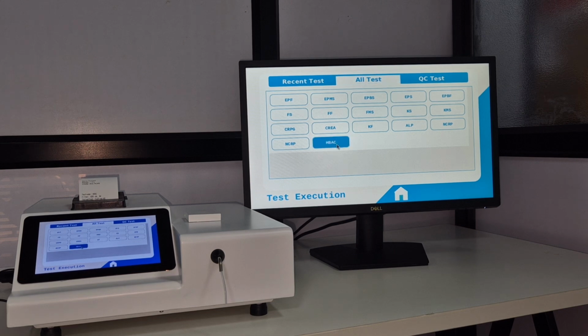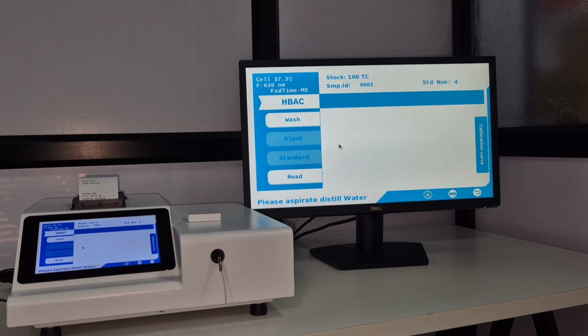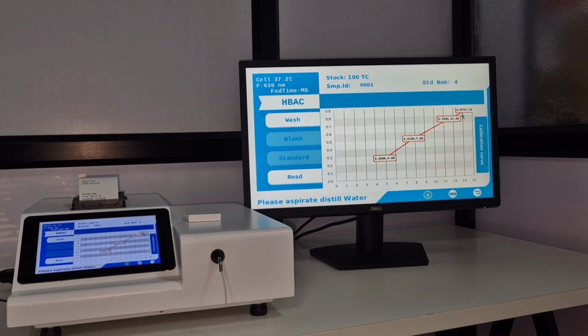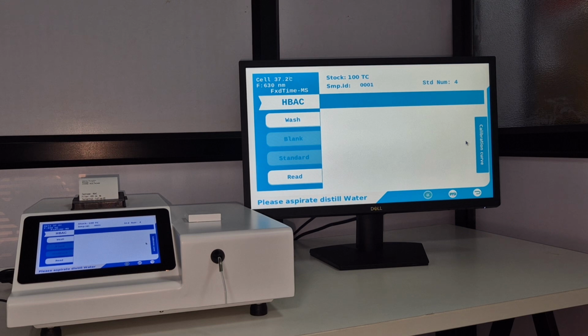The most important thing is that HbA1c is such a tedious test, requiring a multi-standard calibration, where not only is the reagent expensive but the multi-standard calibration method is also tedious. So again we have made the technician's life simpler by making the calibration curve for the particular lot, and this calibration curve is available on the web server. The technician can download it, something like this. This calibration curve was stored in the web server and is being downloaded. Thereby any kind of multi-standard calibration can be avoided: when he takes the reagents from the authorized supplier or authorized distributors, he will find the curve on the web server and can avoid doing the multi-standard calibration.